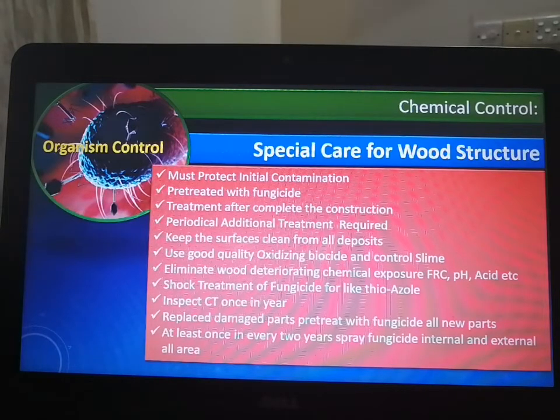After installation, the system must be kept clean. All internal and external cooling structure, the wooden structure, must be clean. It must be cleaned using chemistry in a strategic manner, by mechanical cleaning, and by periodic maintenance cleaning, but it must be clean. We can't keep a surface under slime or microbiological contamination for a long time, like 6 months to 1 year, which is very dangerous. There must be a plan for yearly cleaning.